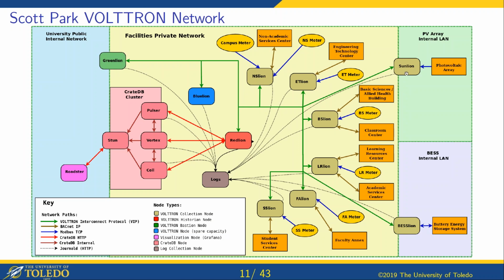The photovoltaic array and the battery systems both use Modbus for communication. The photovoltaic array is not controllable; we're only pulling data from that and storing it. And the battery, of course, is controllable—it wouldn't be very useful otherwise. In fact, our controller for it is written as a VOLTTRON agent and runs on this node that talks to the BESS and communicates with it over Modbus.